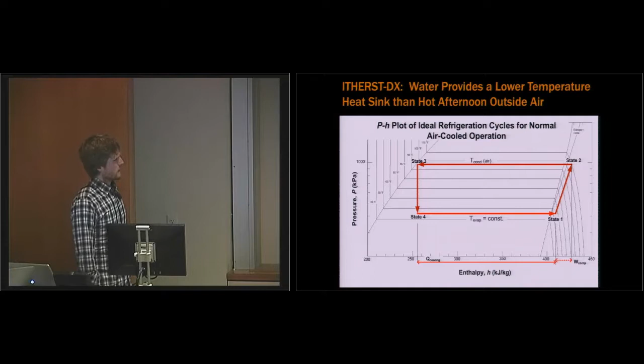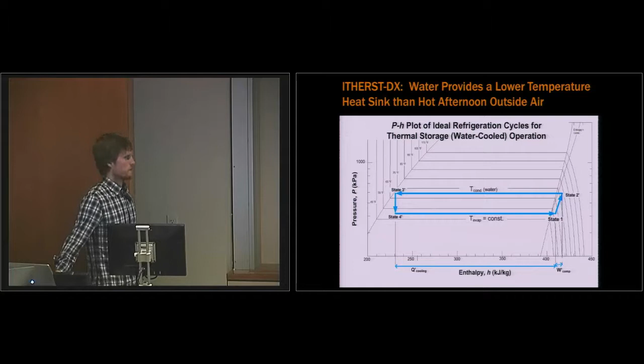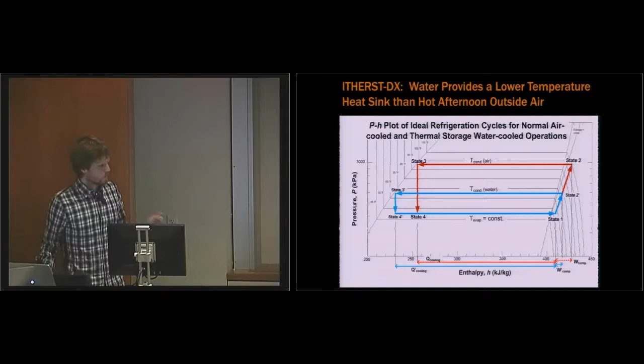When you're using the outdoor air, you have to compress it up to this pressure so that you can condense it at that temperature. When you use water, you're pressurizing it to a much lower pressure because the water's at a much lower temperature. This has a double benefit. It requires less power, and you get more cooling. So it's a double whammy of good things that happen when you have a lower condensation temperature.